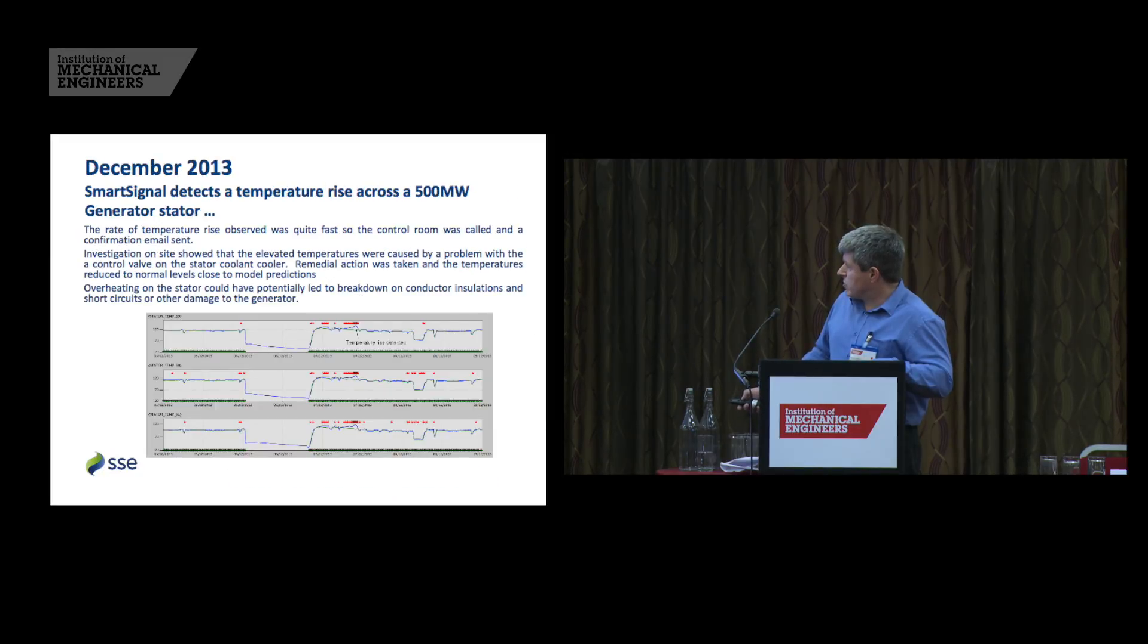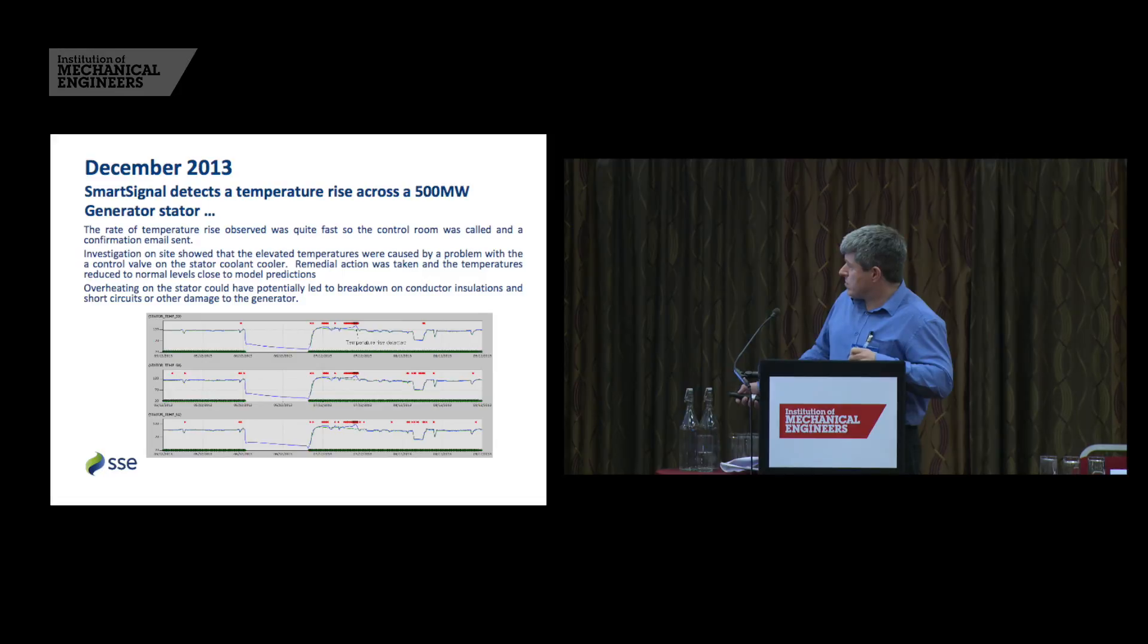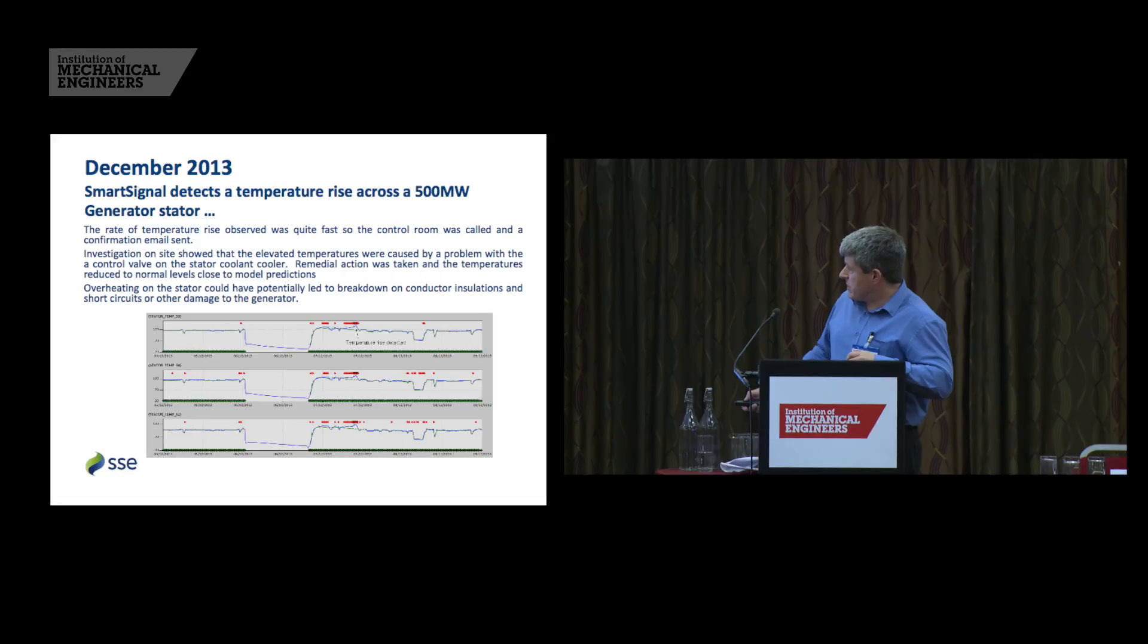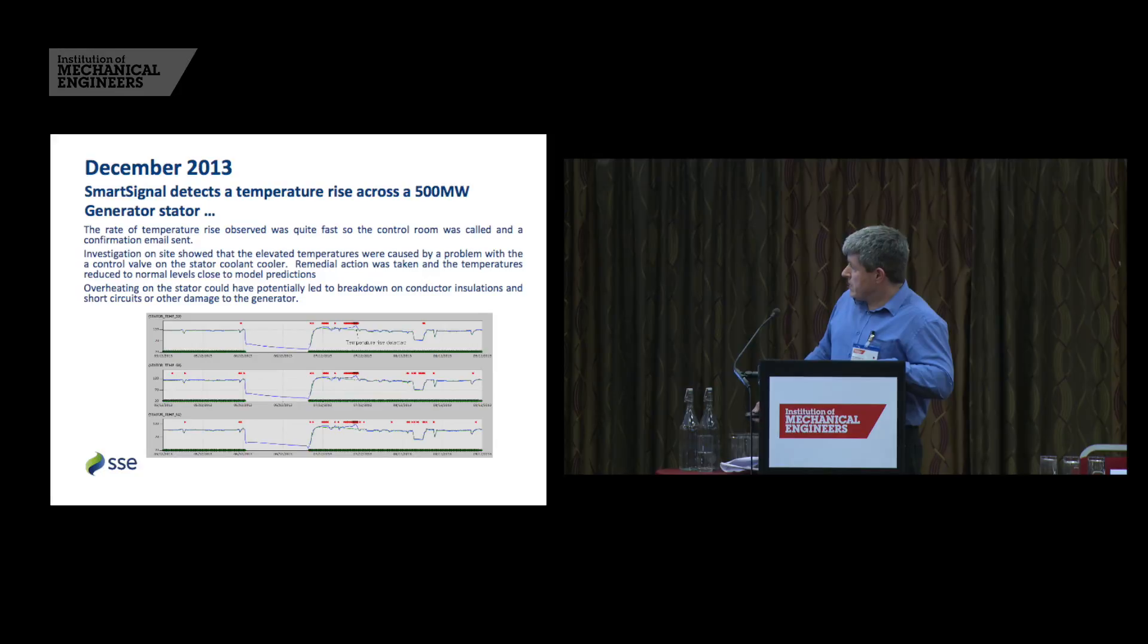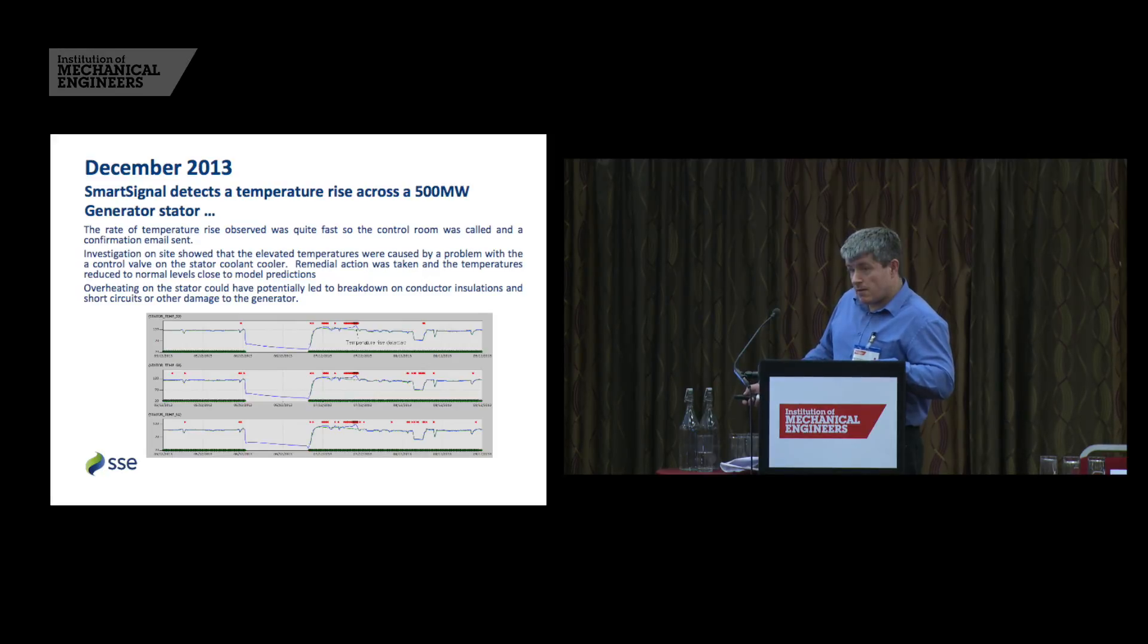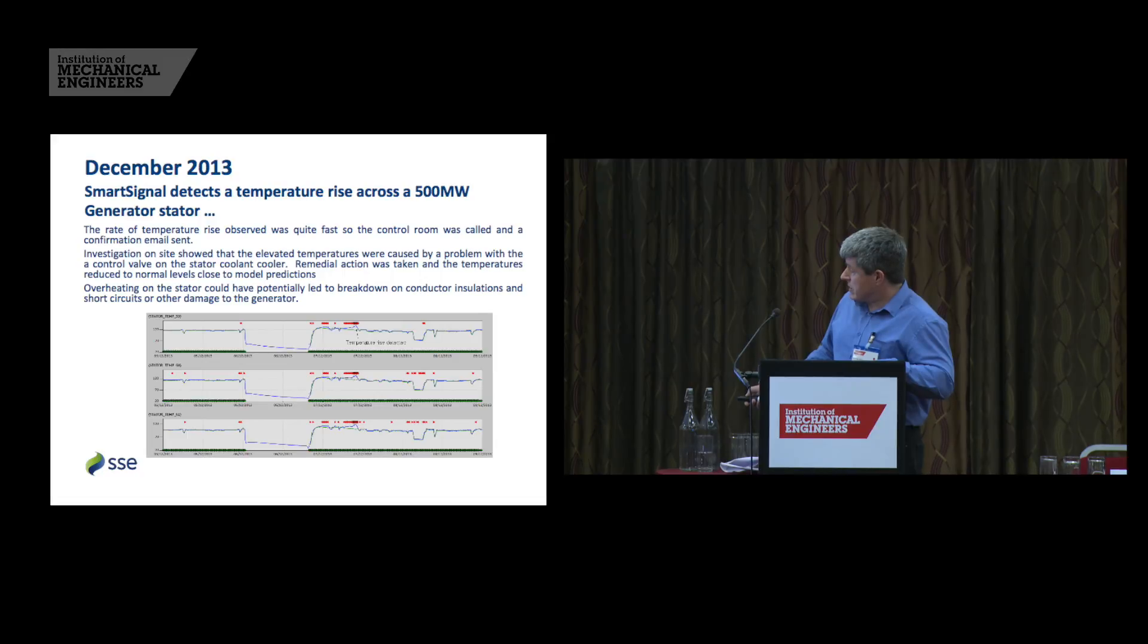Finally, just a quick example. This one was 500 megawatt generator stator temperature rise. We picked up a temperature rise here and then suddenly it started to rapidly increase. And we phoned the operators and they went and checked it out. And it was a problem with a control valve on the stator coolant cooler. So the remedial action was taken. And again, the temperatures then dropped back down to the estimated levels. And we can see from this one how well typically that the smart signal model tracks the actual.